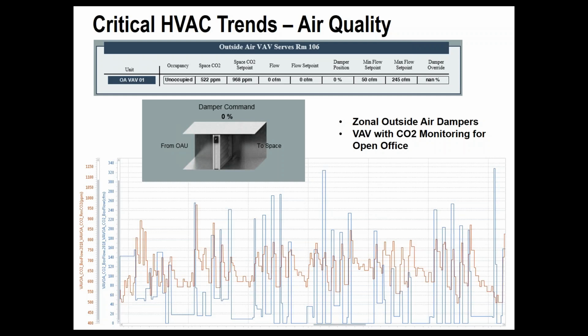So what I saw here was that the damper for that one demand control ventilation zone seemed to be working pretty well. But I thought there was an opportunity here to do additional verification in those other zones that don't have CO2 sensors. And the opportunity for improvement here would be to install CO2 sensors for tracking purposes in those other zones to make sure that the outside air is actually meeting the needs of how those spaces are being occupied.